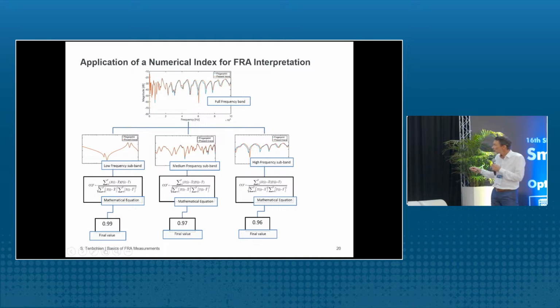So we have here the full FRA. We investigate here the low frequency band, the medium frequency band, and the high frequency band. Then we apply the formula, and then we have a final value, 0.97 here for the medium frequency. So this is first an objective value. But of course now the question is, what is a correct limit? What should be the value for a good transformer, and what should be the value for a bad transformer?